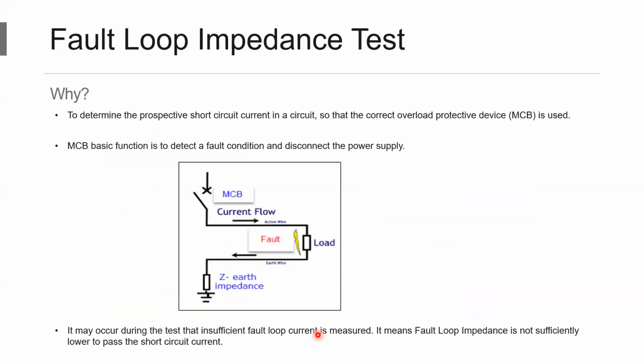So why does the fault loop impedance test have to be done on site? This is to determine the prospective short circuit current in the circuit, so that the correct overcurrent protective device, that is the MCB, can be used. So first of all, we should know the type of MCB to be used, when I say the type, the characteristics of the MCB as well as the rating of the MCB to be used when we want to have overcurrent protection in the case of elevators. Now, if the fault loop impedance test is not passing, it means the fault current is insufficient to flow, or the fault loop impedance value is higher, and there could be various reasons why the fault loop impedance is high.